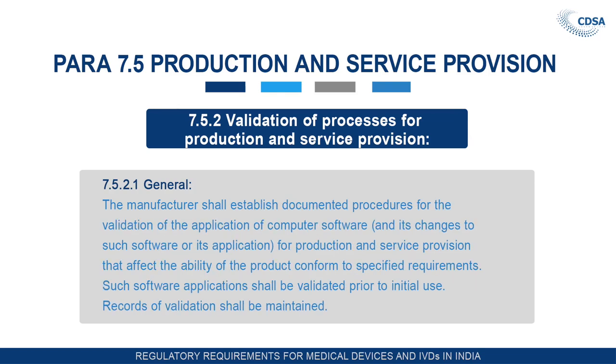Manufacturers shall establish documented procedures for the validation of the application of computer software and its changes. Now, in this case, it's a computer software validation. The devices that are notified at the moment do not require any computer or software for their running. These are required in high-end medical devices, in the range of say MRI and X-ray machines and all those equipment which require software for its running and application. So, that software or computer system has to be validated again.